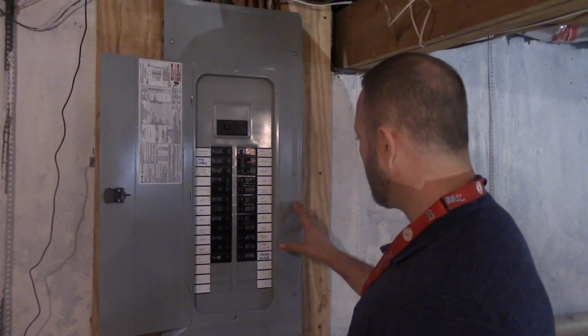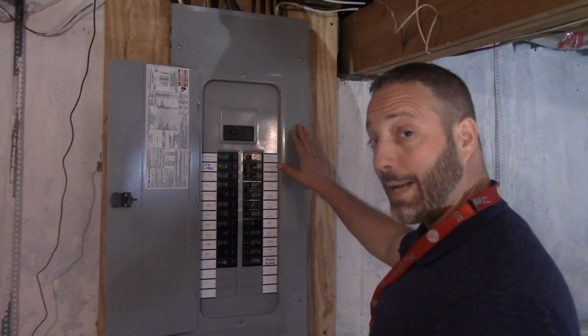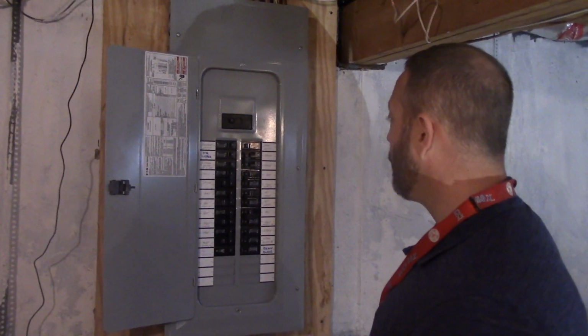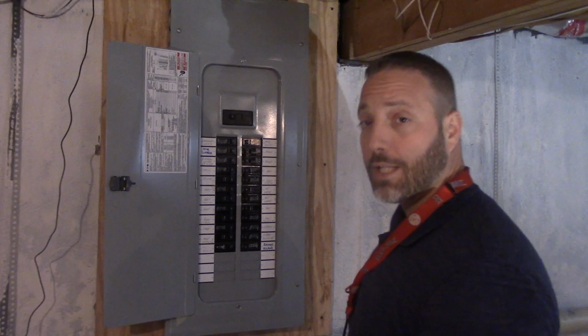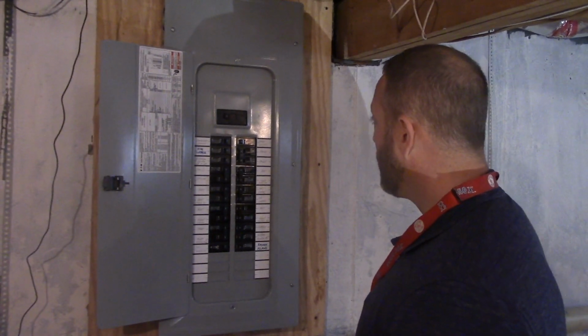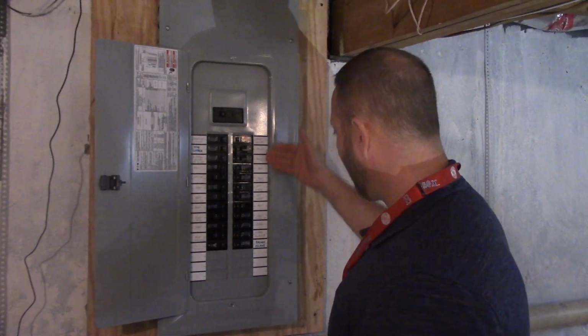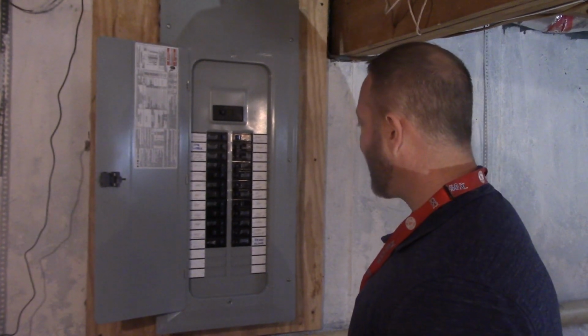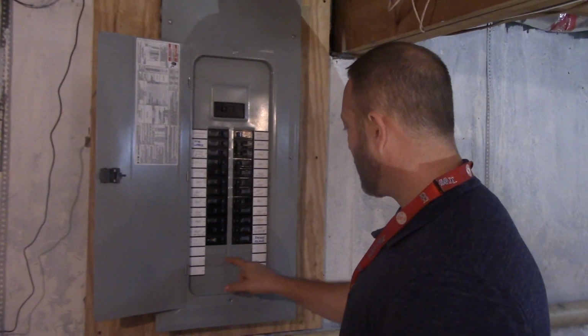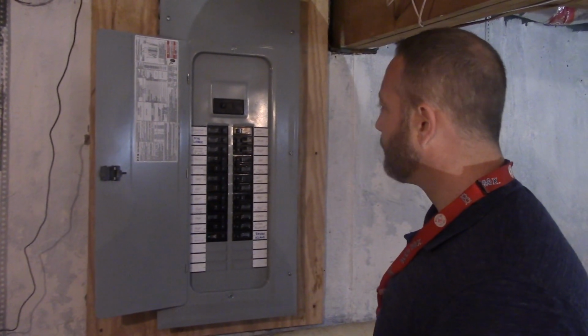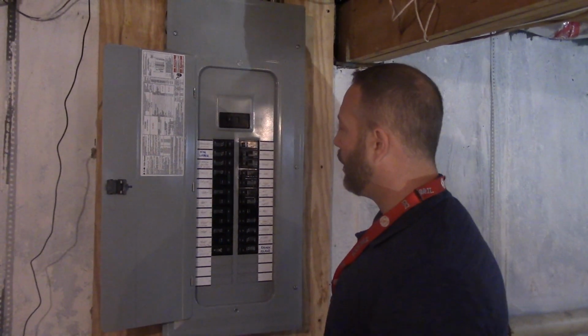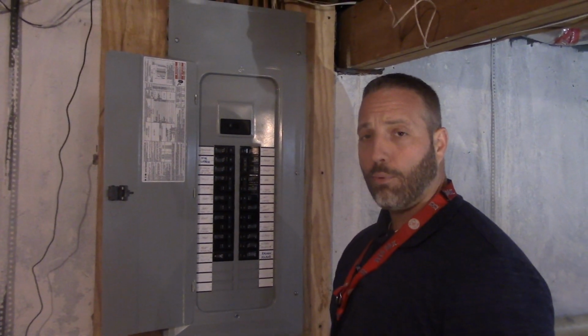So when you have a licensed electrician that installed the panel, a third party is going to go and ensure that it was done to the NEC code. All right, so while we're looking over here, we can see that items are properly labeled. We don't have any missing or any open slots. And then we can see that we have a 150 amp breaker.